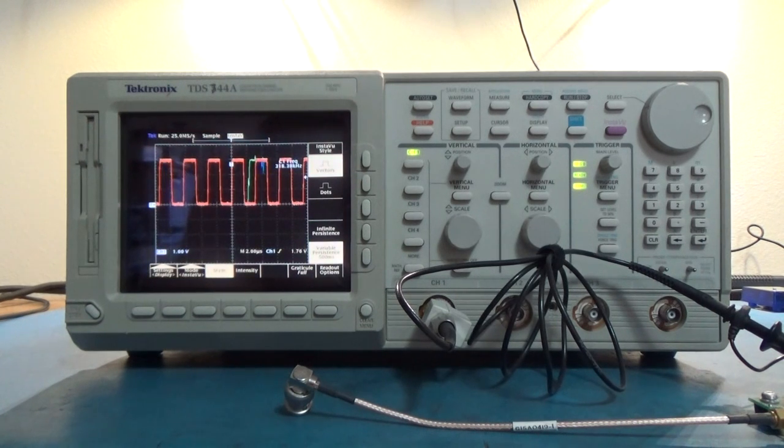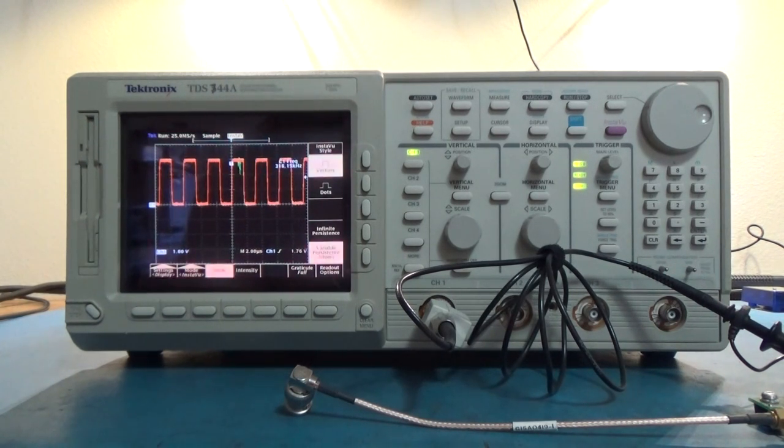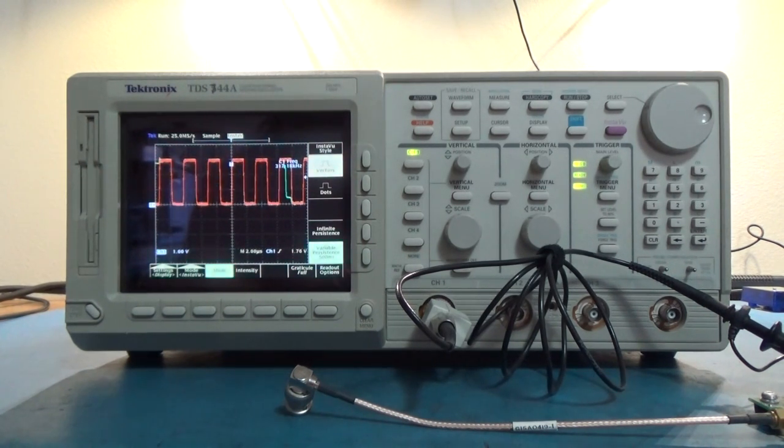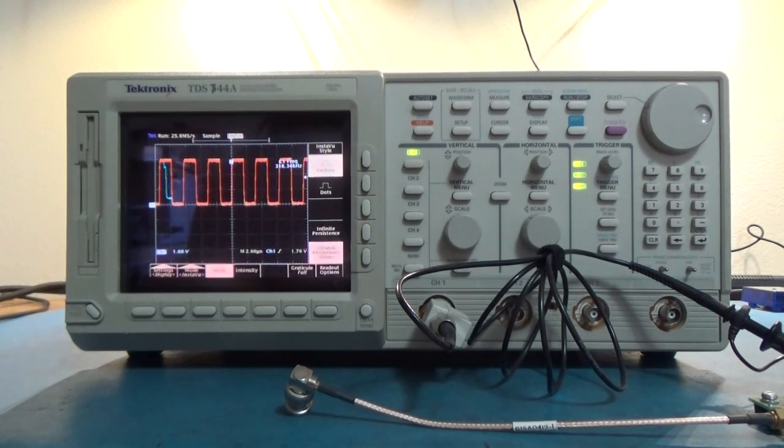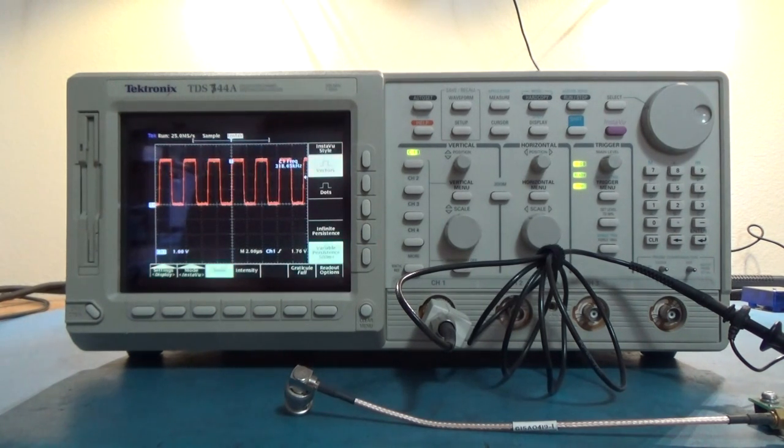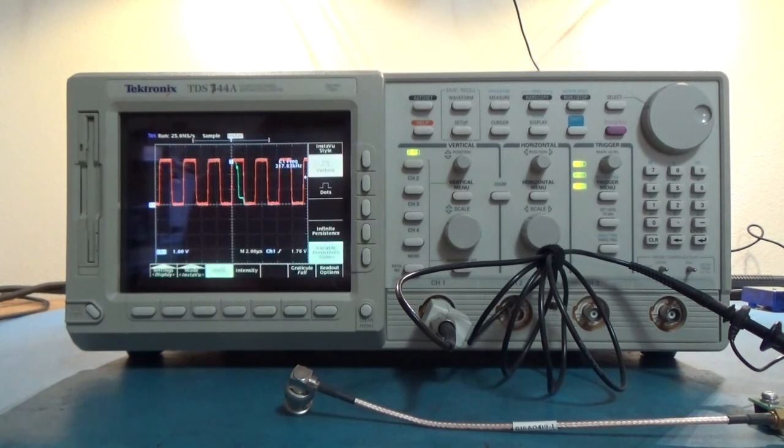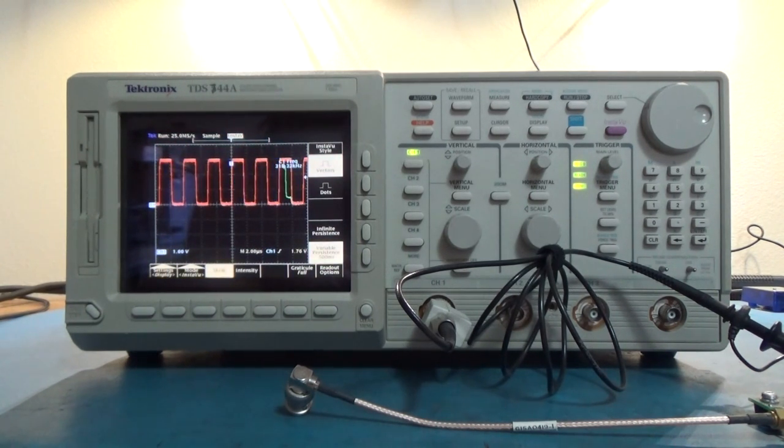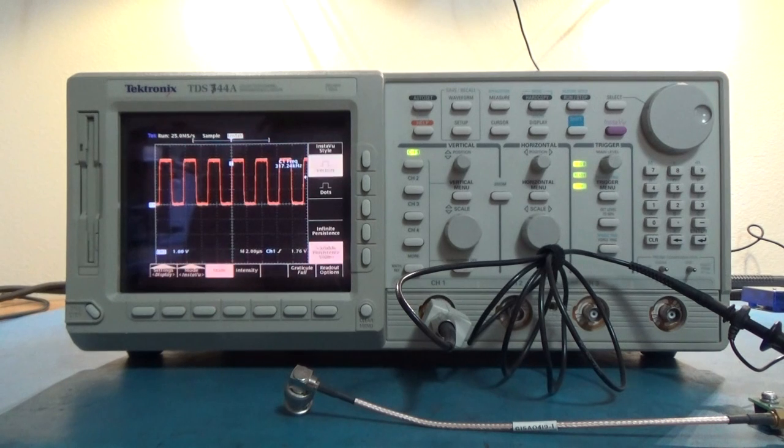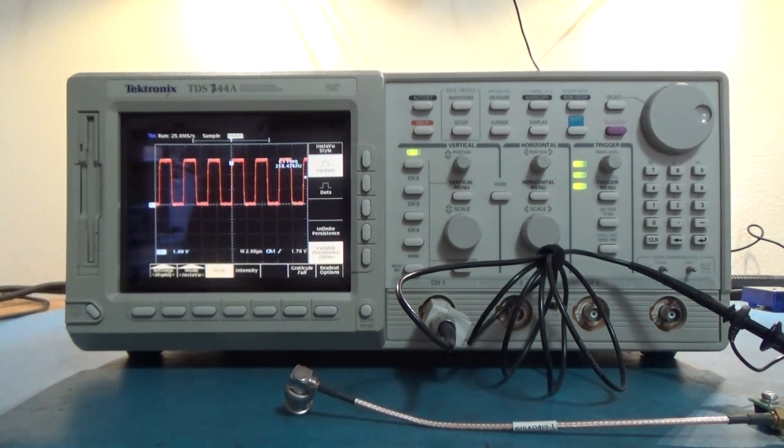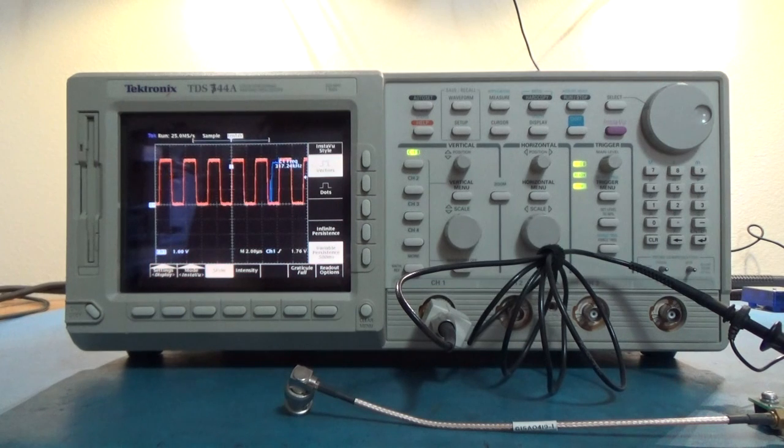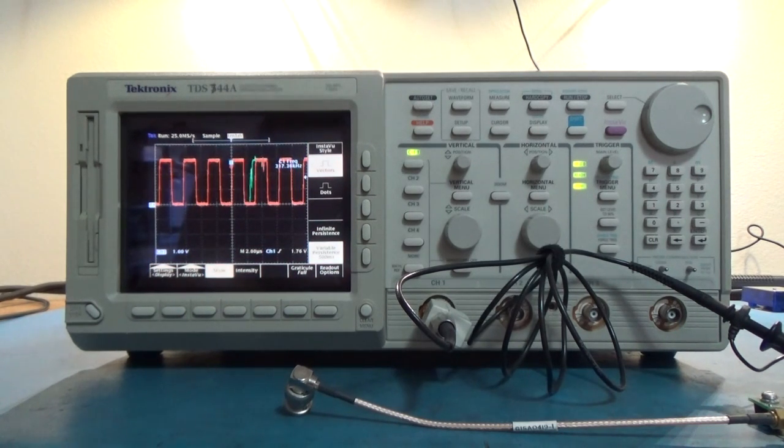Things that go wrong with these, the earlier scopes, the attenuator's almost never failed on those. But on this family scope and later, it's always the attenuator if there's an acquisition problem, unless there's been physical damage to the board. The display will get tired, it can get bubbling on the screen.